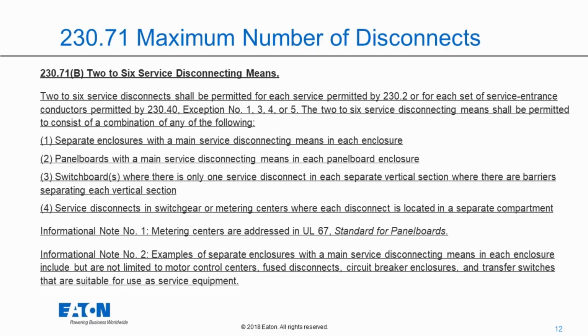And I'm going to show you some examples of what might be questionable with regards to compliance with option number 3. And then finally, option number 4, service disconnects in switchgear or metering centers where each disconnecting means is located in a separate compartment. And they do provide an informational note that those metering centers are addressed in UL 67. The real challenge with this is, if you look in UL 67, there is no guidance for compartmentalizing meter centers, so it really becomes very difficult to do that.